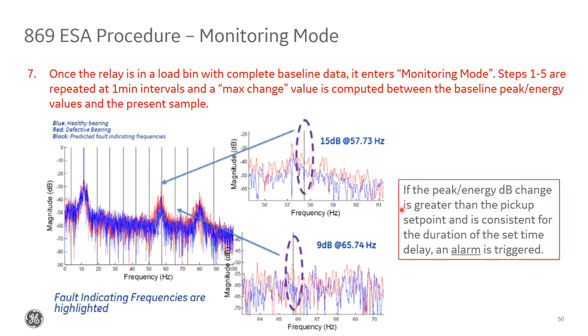When we're finally in monitoring mode, here's where we continuously do a comparison. We take the baseline recorded values, which are assumed to be the healthy motor values. That's the blue curve shown here. And we compare that to the currently sampled values, the red curve here.